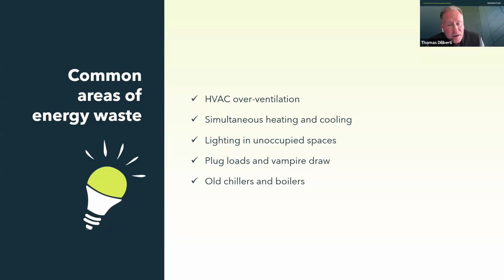The other issue is that these sophisticated facilities can simultaneously heat and cool - a building has the ability to produce both heat and cooling, so the systems can fight with one another. If the sensors aren't calibrated correctly or the system isn't working properly, you can essentially be paying two bills - paying to heat and cool the facility simultaneously. You need to understand if your system can do that, and how to adjust it by changing settings. There are mechanisms within the building automation system for what's called a dead band - a series of temperatures where you heat, cool, or do neither, to keep people comfortable. Make sure you understand what those settings are and how they're set, and that people are trained, because someone might be making decisions for the system while confused, and it ends up simultaneously heating and cooling.